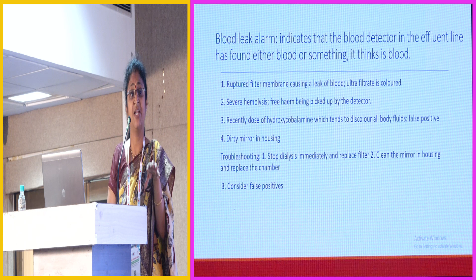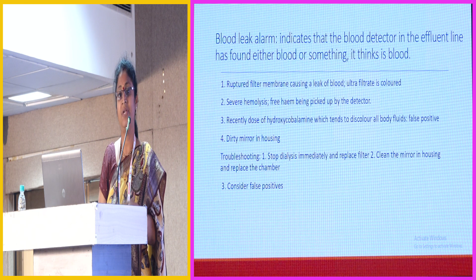So this is very important. And the fourth one is dirty mirror in-housing. I must thank the technicians in the NIMS department, because when we open the machine and we see, if the technician is really well versed with the machine, he cleans the mirror in the blood detection mirror. If you are not properly cleaning that mirror, and there is dirt in the mirror, you get frequent blood leak alarms. So you should identify that. Our goal is not to get the alarm or try to correct it at the first, because we are going to decrease the delivery dose.